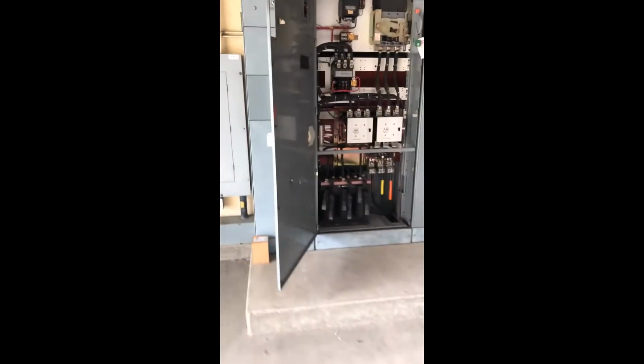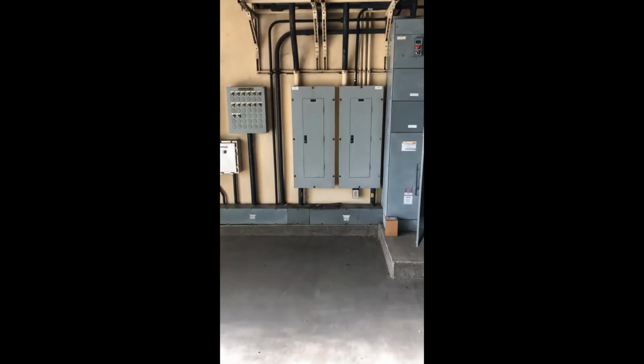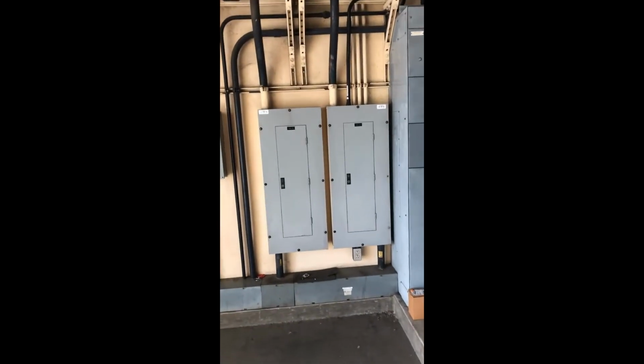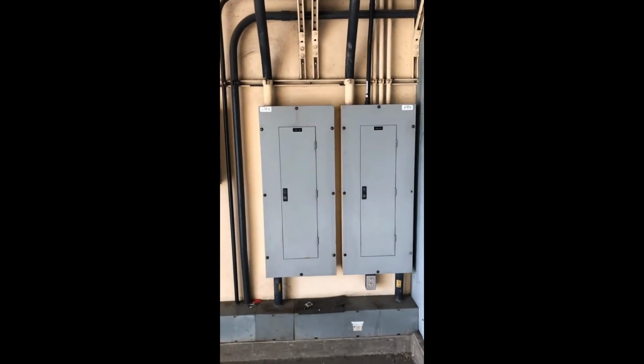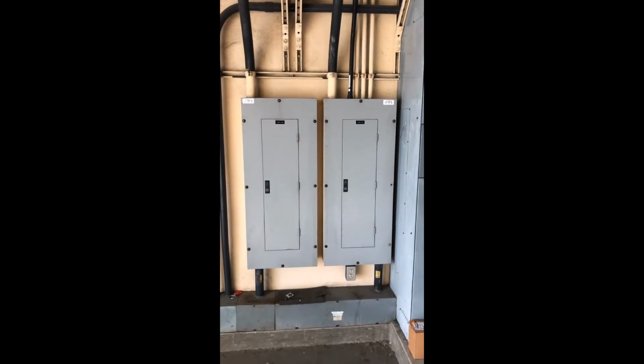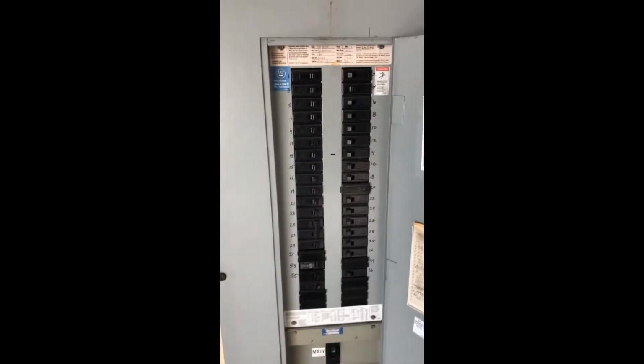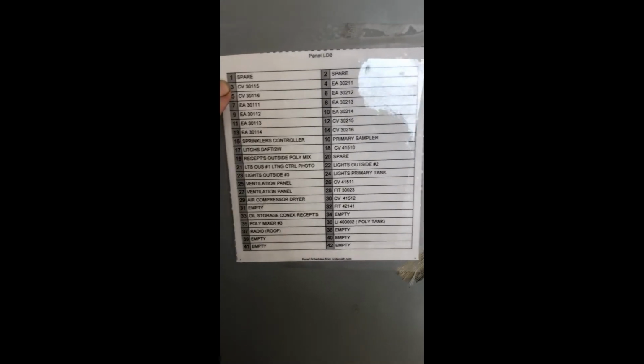See, while I'm up here, here's our lighting panels. So throughout the plant, we have outlets, we have instrumentation, we have all kinds of things that don't require 480 volts. And so this is very similar to what you probably see at your house. These smaller circuit breakers, this is where they're going. These ones on the left here, CV is a control valve, so we have some motor operated valves that are 110 volt. Sprinklers, some lights, some receptacles, all kinds of stuff here.